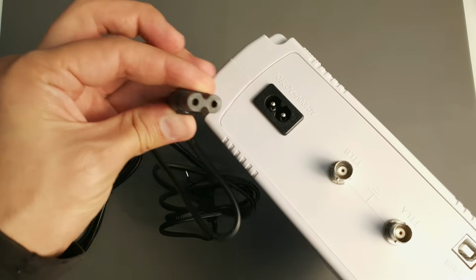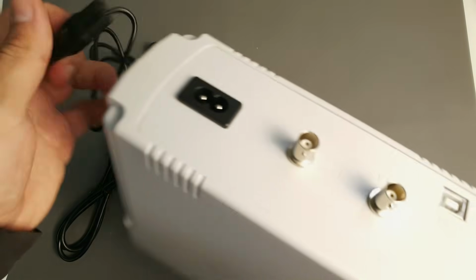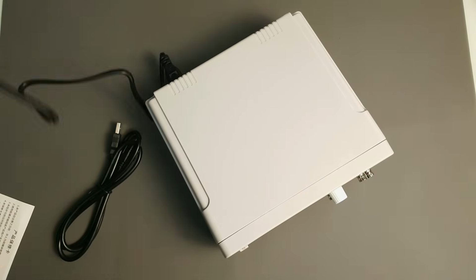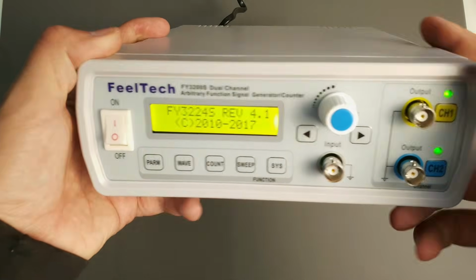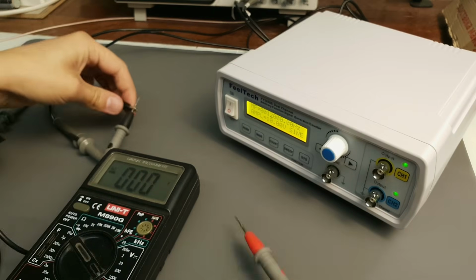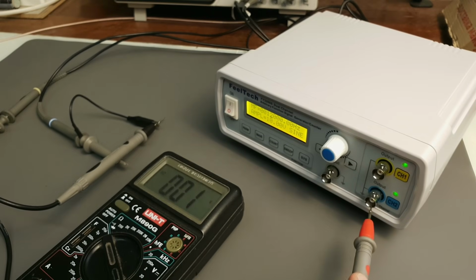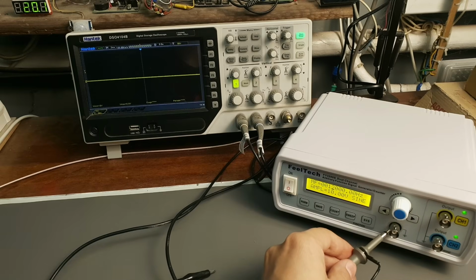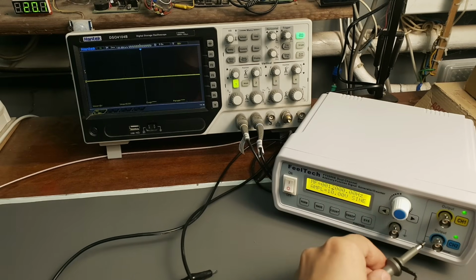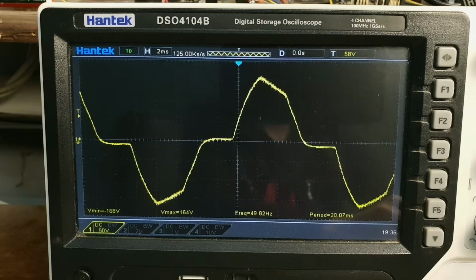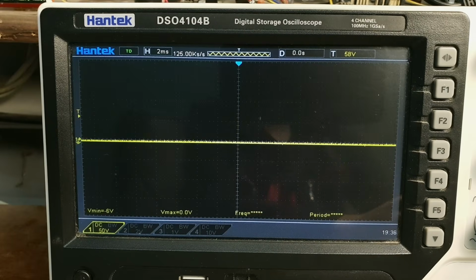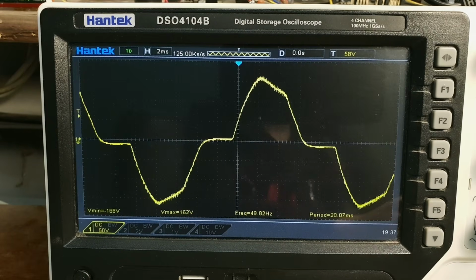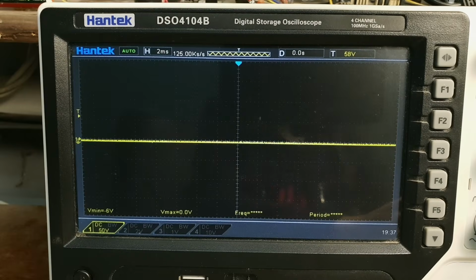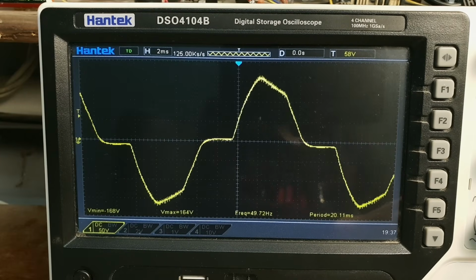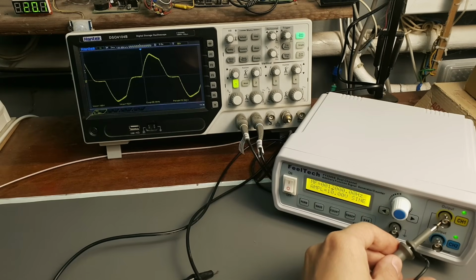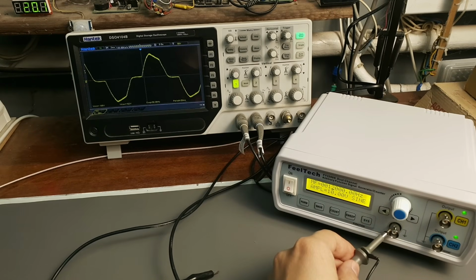And of course, right away there is a problem. Only 2 pins on the power inlet, no ground wire. I'll show you why that matters in a moment. Let's power it. Let's measure voltage between actual ground and what's supposed to be ground. Multimeter shows 82 volts AC. That's already bad, but let's take a look at it on the oscilloscope to understand better. The scope shows voltage swings from plus 160 volts to minus 160 volts, and that is on the ground side of the BNC connector. Looks dangerous, but it will not electrocute you because the current is very low, but it surely can damage sensitive electrical devices, so grounding is needed.